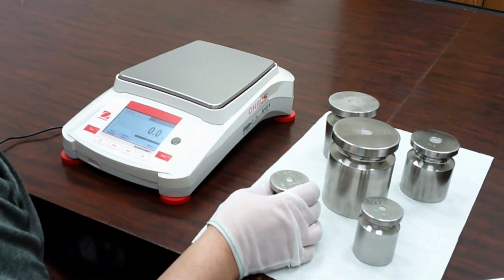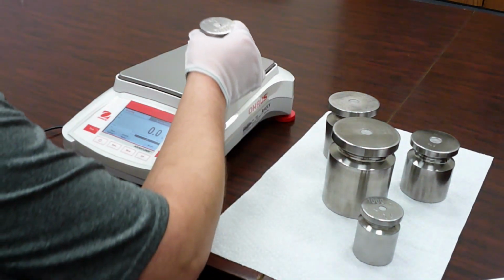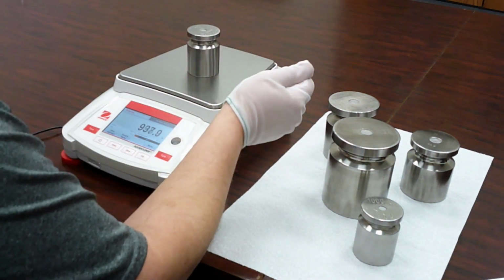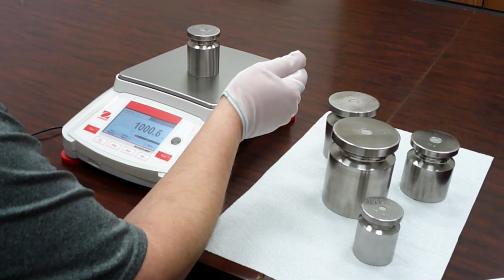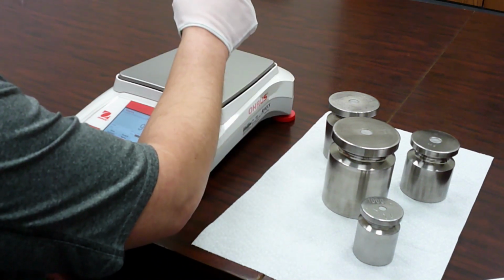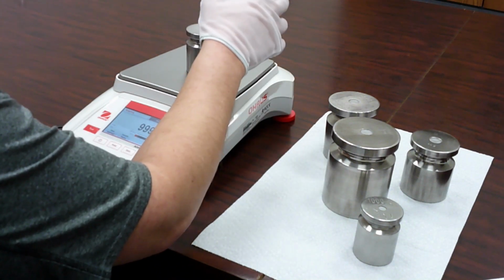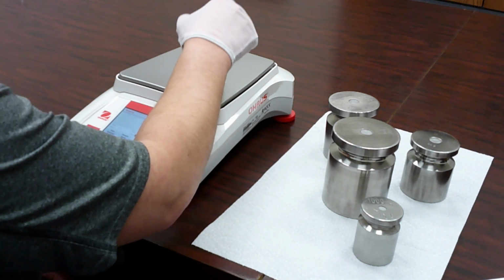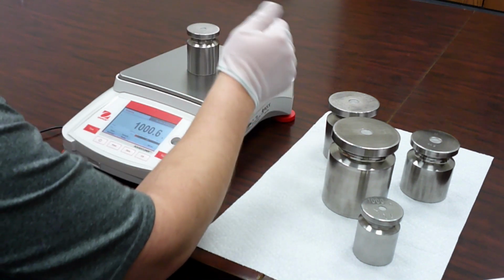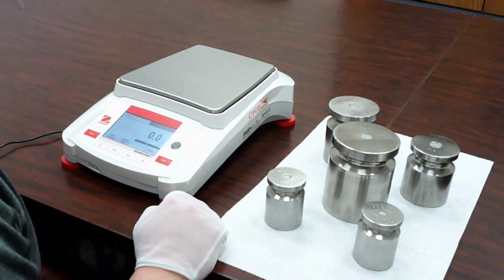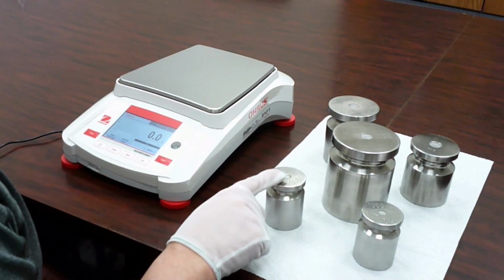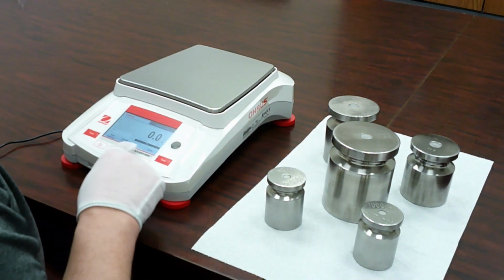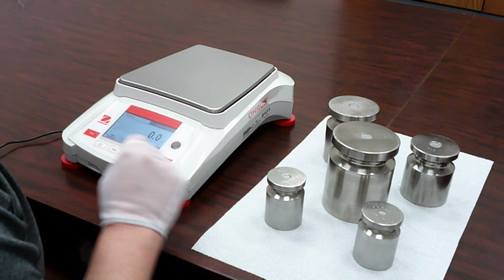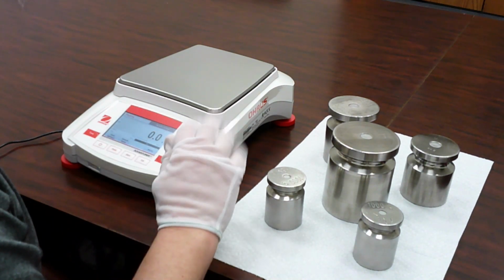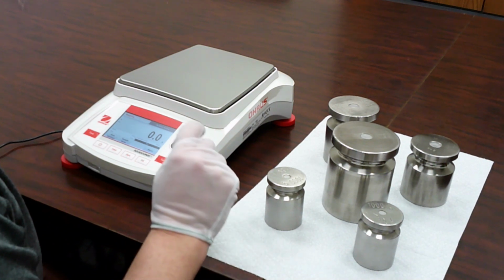First, we want to exercise the pan by adding and removing the weight a few times. This will ensure that there are no components, external or internal, that are sticking. We're not concerned about accuracy at this point. Now we want to go ahead and apply weights to the balance to check the accuracy. We use at least 4 different weights to check the balance throughout the range of the capacity. We also are checking to make sure that the balance is linear throughout.